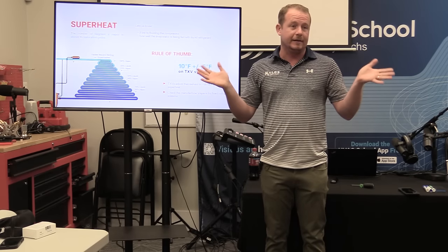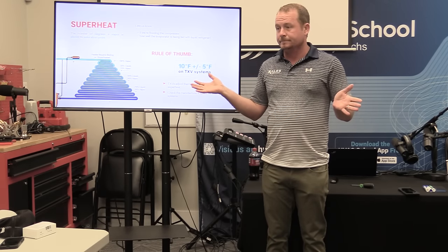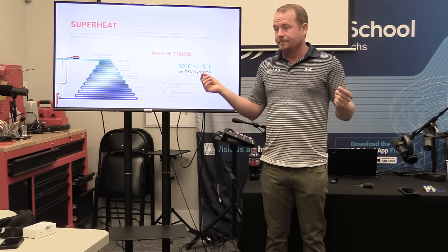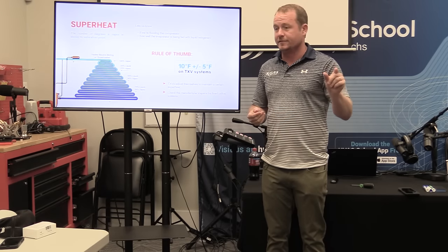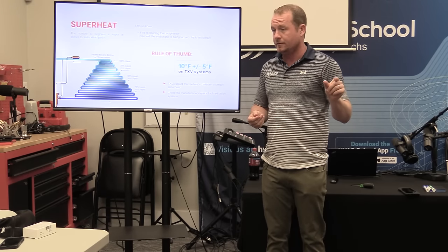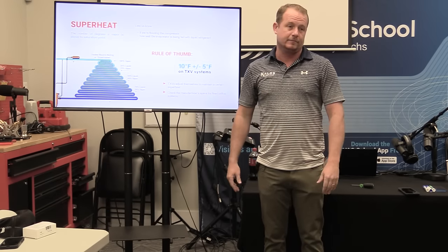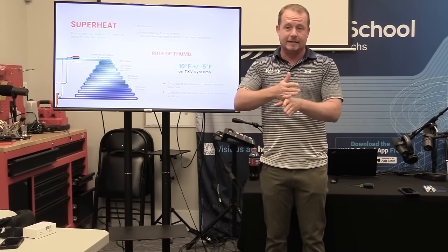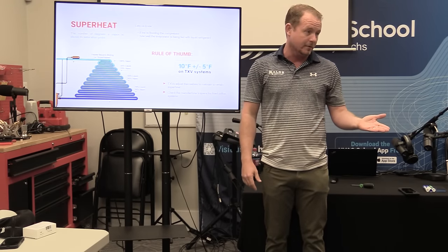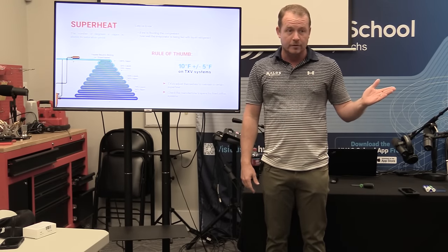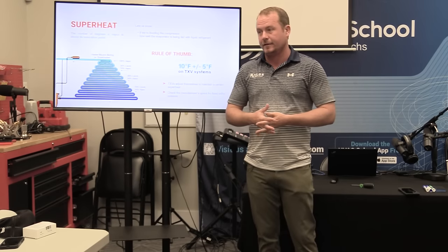How do we measure superheat? It's the difference between suction saturation — otherwise known as evaporator temperature, what you're reading on the gauge — compared to the actual physical line temperature. That's all it is. The physical line temperature is always going to be higher. You can't have negative superheat, you can't have negative subcool. If you do, that means there's a measurement problem — something's wrong with the measurement you're taking.